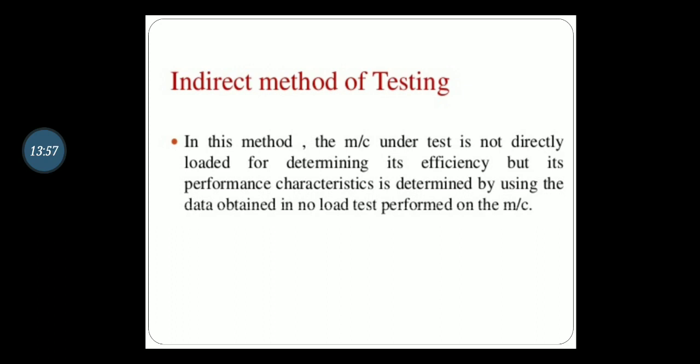The power is required to supply the losses only, so there is no difficulty in applying this method even to very large machines. The disadvantage of this method is that the machine is run light during this test, which gives no indication of the temperature rise on load or of the commutating qualities of the machine.